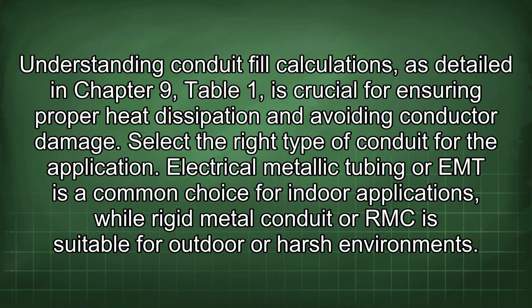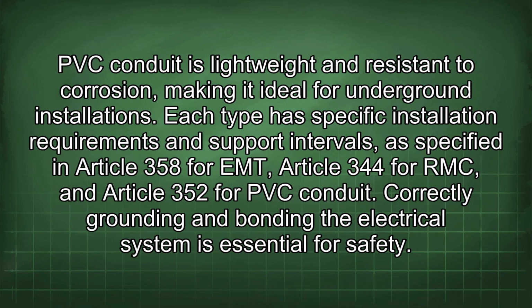Select the right type of conduit for the application. Electrical metallic tubing, or EMT, is a common choice for indoor applications, while rigid metal conduit, or RMC, is suitable for outdoor or harsh environments. PVC conduit is lightweight and resistant to corrosion, making it ideal for underground installations. Each type has specific installation requirements and support intervals, as specified in Article 358 for EMT, Article 344 for RMC, and Article 352 for PVC conduit.